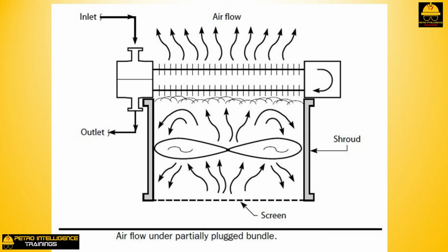Walking across a fin tube bundle will crush these fins. It looks bad but does not appear to affect cooling efficiency.